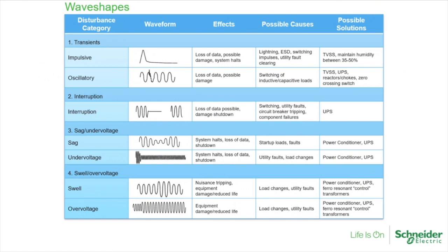All right, the next couple of tables are going to go over different wave shapes, an example of the waveform, their effects and possible causes, as well as possible solutions. So we talked about transients, impulsive and oscillatory. They can cause loss of data, possible damage, as well as halting the system. For impulsive, this can be lightning, switching impulses, or utility fault clearing. Possible causes for oscillatory transients are usually switching of inductive or capacitive loads, like when you're switching the cap bank, switching it out. And different solutions can be a universal power supply, zero crossing switch, as well as reactors and chokes.